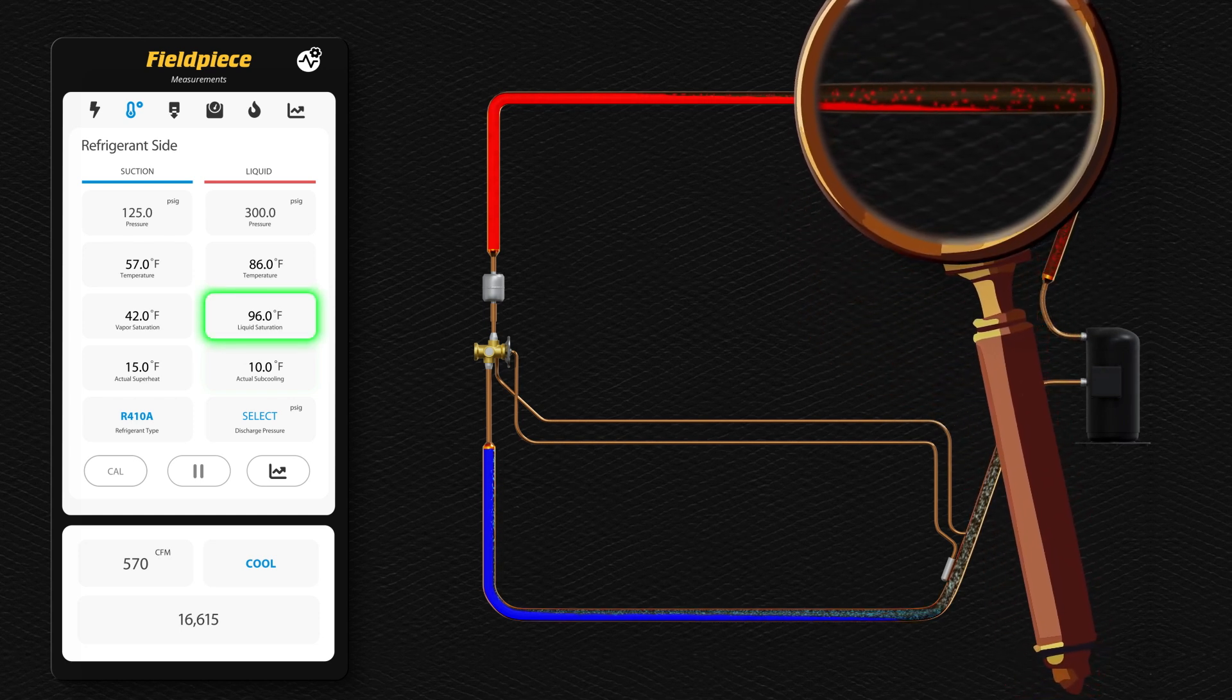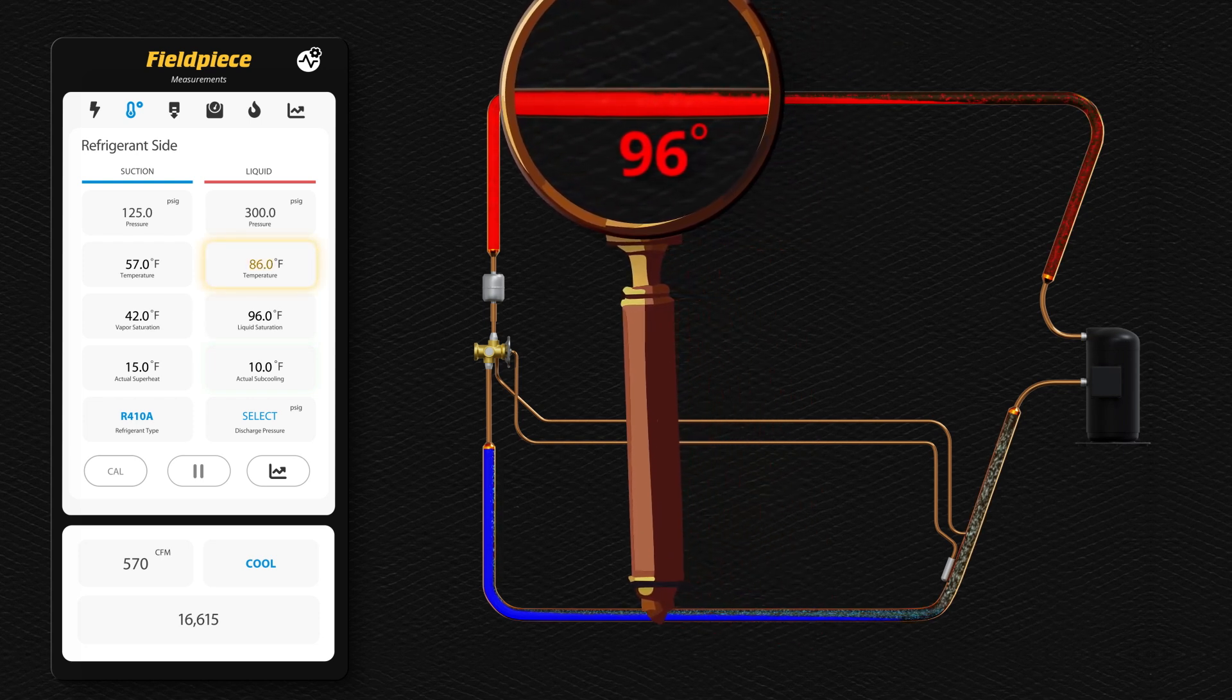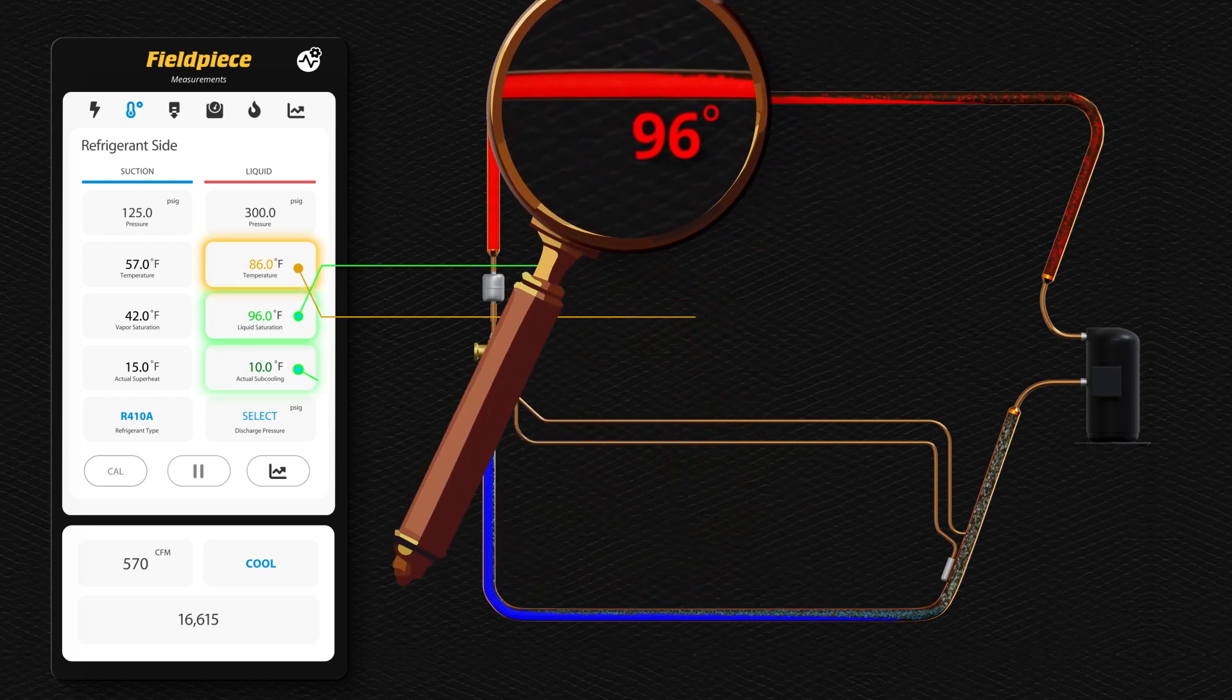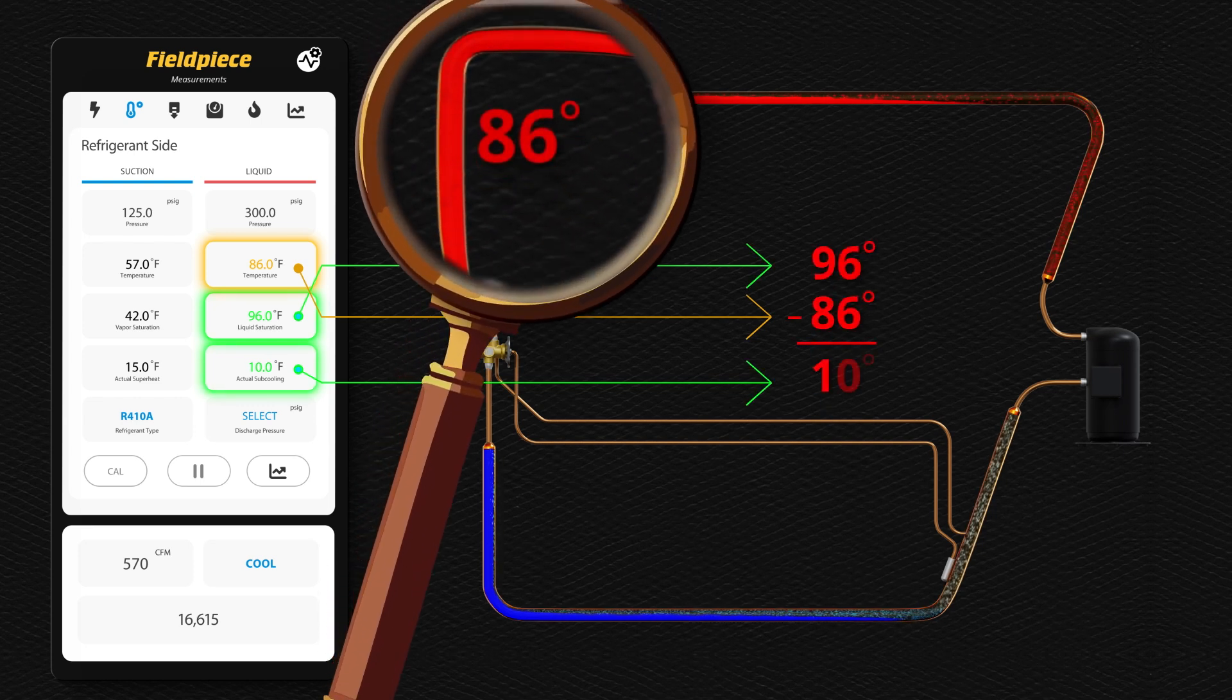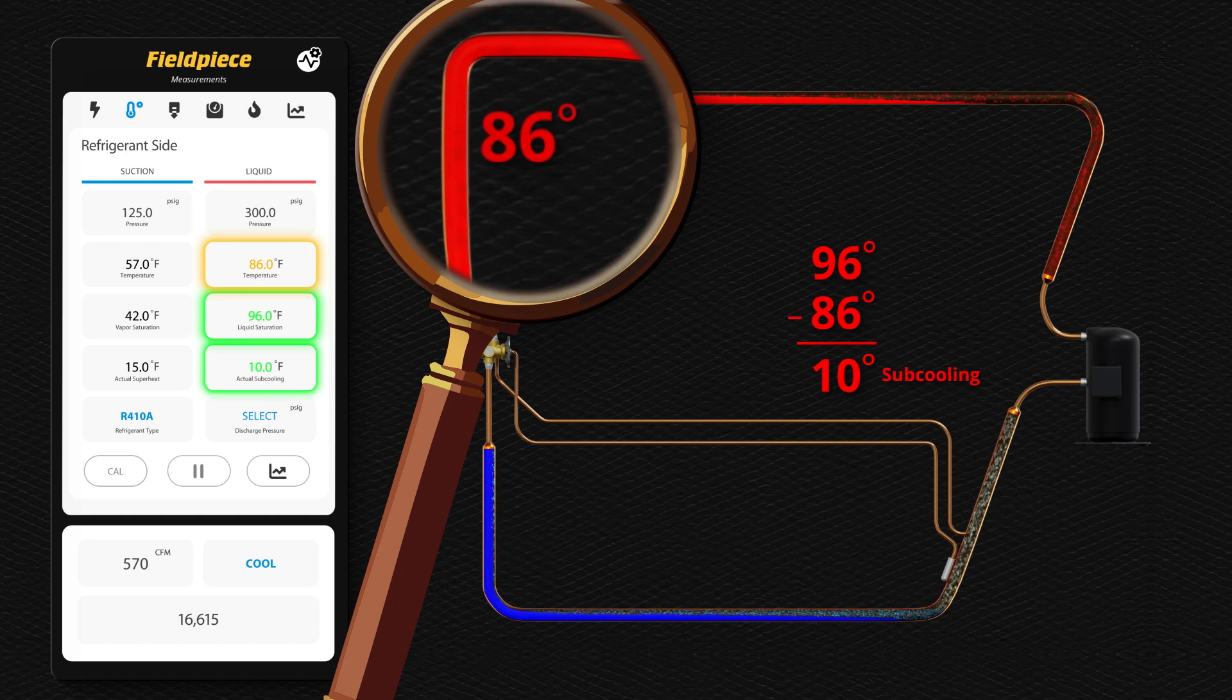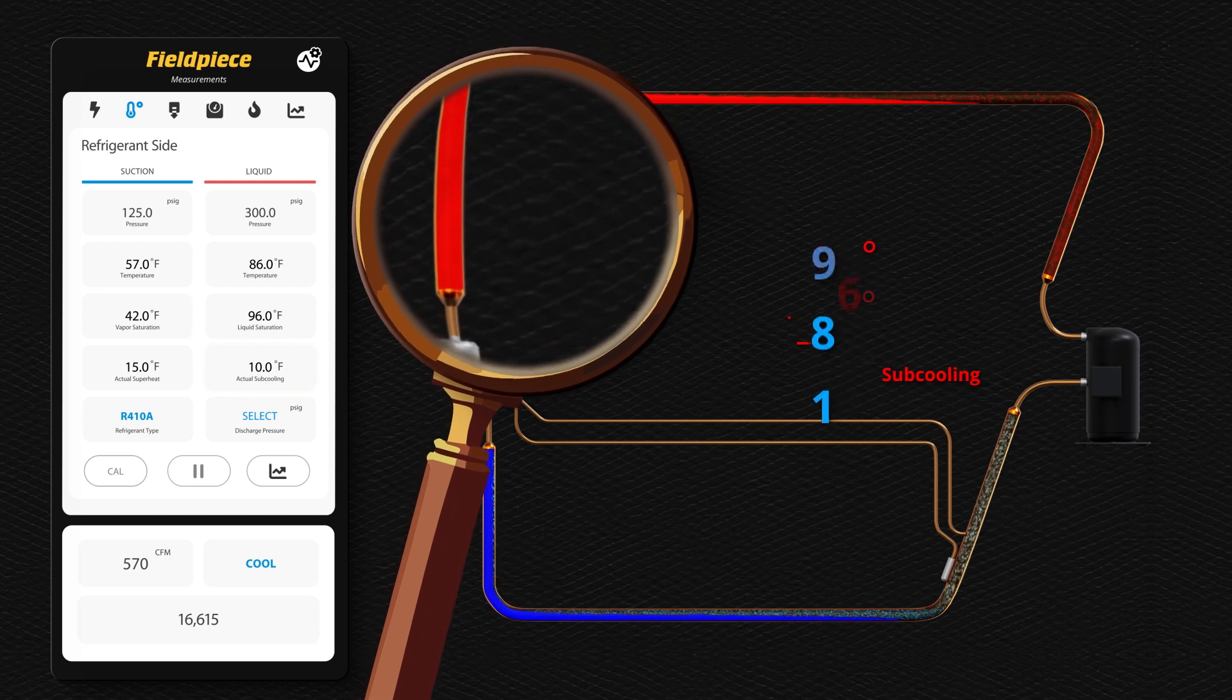As the temperature travels further through the circuit, the saturated temperature remains at 96 degrees, but the actual refrigerant temperature equals 86 degrees when it leaves the condenser. Since the refrigerant is below the saturated temperature by 10 degrees, the refrigerant is 100% liquid with 10 degrees of sub-cooling.